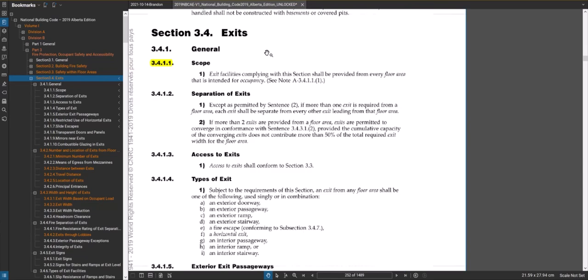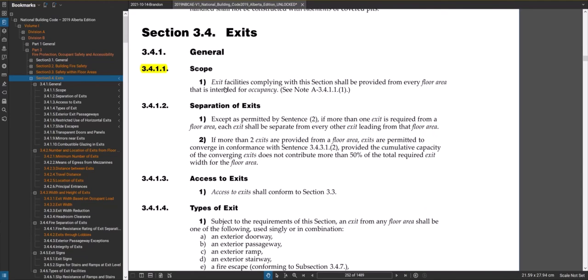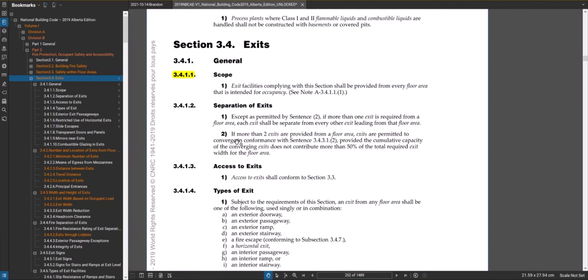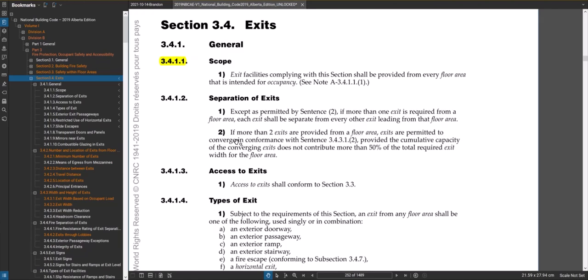Right away when we go here, if you just read the scope for exits: exit facilities complying with this section shall be provided from every floor area that is intended for occupancy. Basically, if you go to the definition of floor area, it'll tell you it's every story — so every floor is going to have to have exits provided from them. Section 3.4.1.2 on separation of exits — generally speaking, exits are separate from each other in most cases. You have one set of stairs on one side of a building, another set on the other side, and they never really converge, but there are some allowances for that.